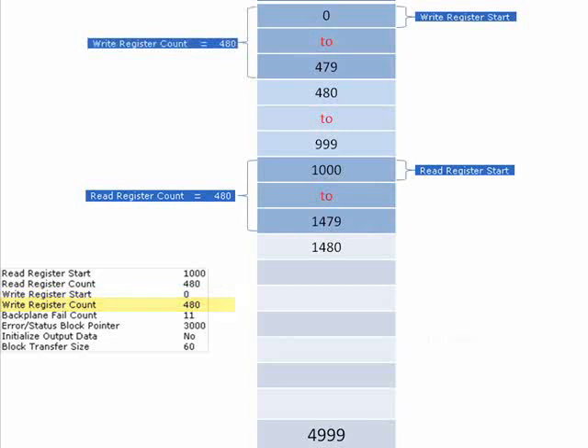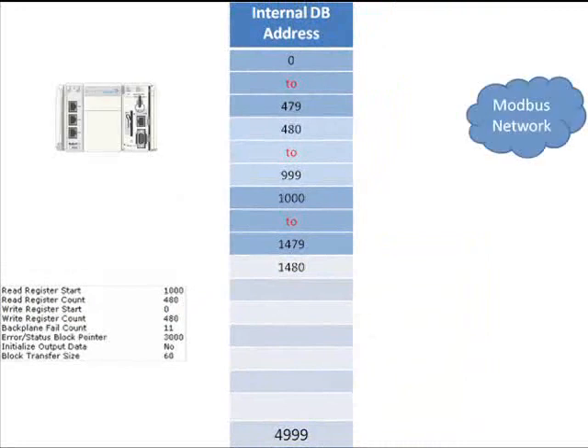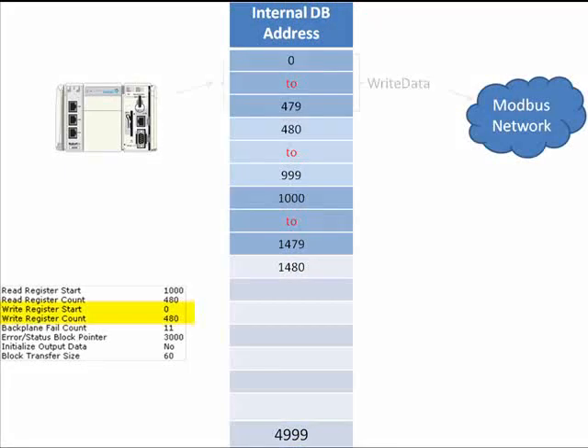We have a highlighted section of unused registers. On the Modbus network, the CompactLogix CPU writes to addresses 0 to 479 of the internal database on the MVI69 module. Those 480 registers can be used to write to Modbus devices on your Modbus network via Modbus master commands. Values from the Modbus network are stored in addresses 1,000 to 1,479 of the internal database.